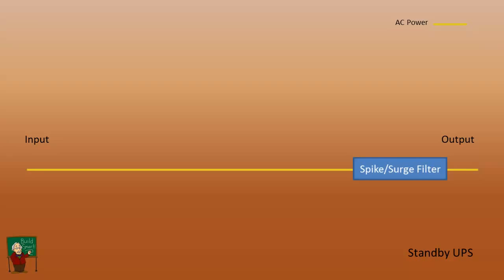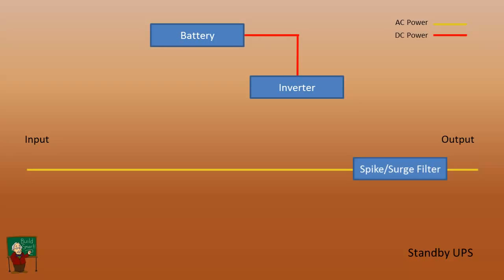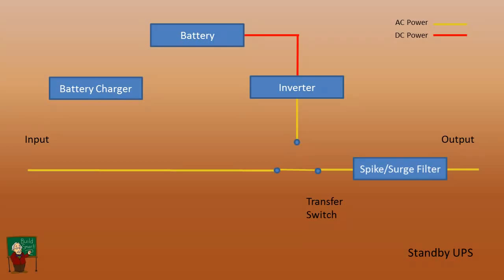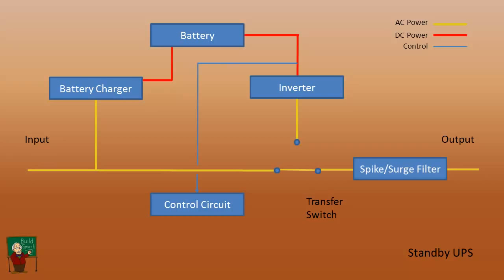This is sort of the lowest level of the UPS, and basically provides a battery backup. So we'll start with the battery and an inverter to convert that DC voltage from the battery to AC. Put those together. And we'll put a transfer switch in line, connect that to the inverter. Put in a battery charger to charge the battery. Connect that to the power coming in, and connect that to the battery. Put in a control circuit. This will be the circuit in place where it receives voltage information from the battery. In turn, it'll be able to turn on the battery charger when that voltage is too low.